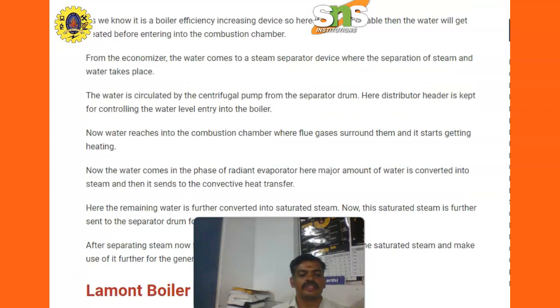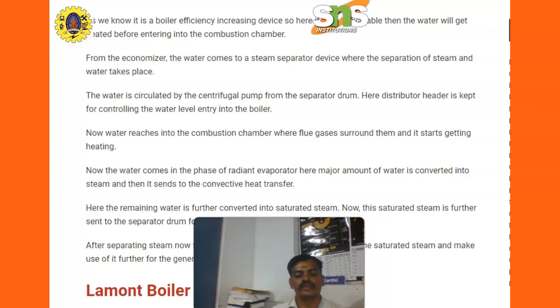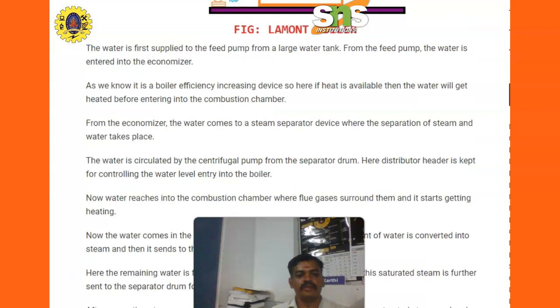The water then passes through the radiant evaporator, where a major amount of water is converted into steam and sent to the convective heat transfer section. Here the remaining water is further converted into saturated steam. This saturated steam is sent to the separating drum for separating steam. After separating, the steam is further sent to the superheater to superheat the saturated steam for use in further generation of electrical power.